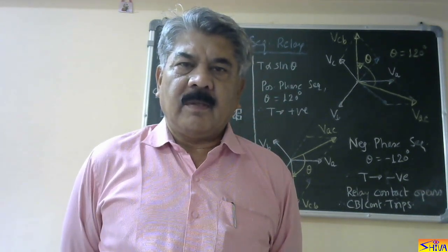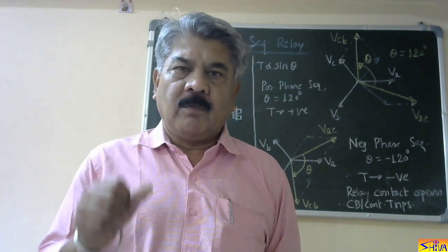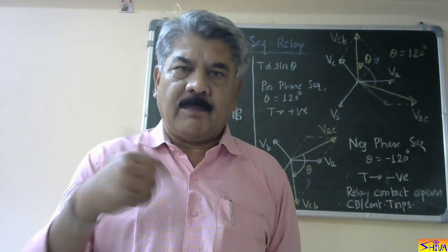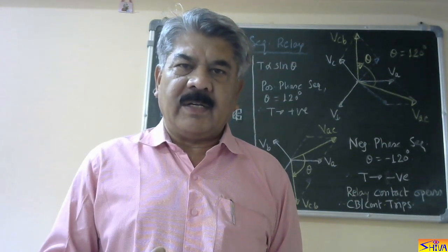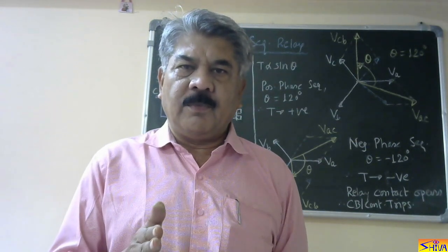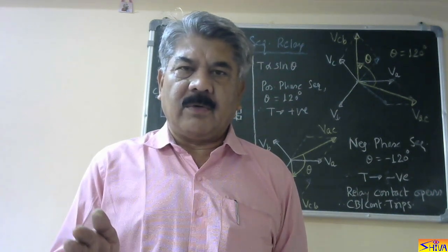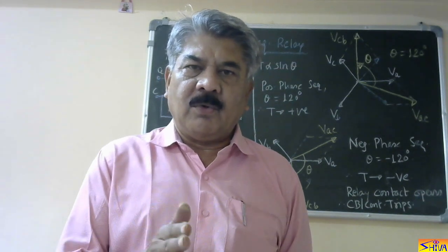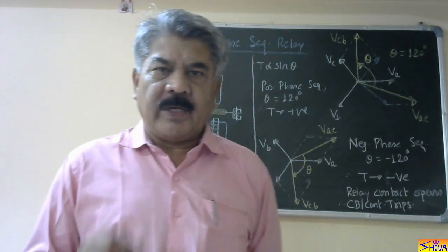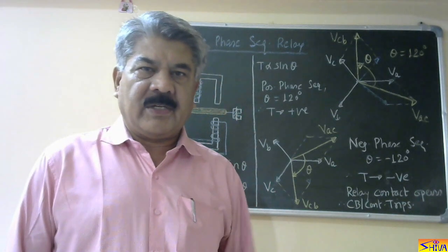Now suppose we want to go in the upward direction in the lift. We want to go from third floor to fourth floor. We press the button. But if phase sequence is reversed, the motor will move in the opposite direction and the lift will move in the downward direction in place of moving in the upward direction. Similarly, in case of a crane, if the operator wants to move the crane in the right direction, and if the direction of rotation is reversed, that is phase sequence is reversed, it will move in the left direction, and this may cause danger. So therefore, protection against reverse phase sequence is necessary in most of the applications.